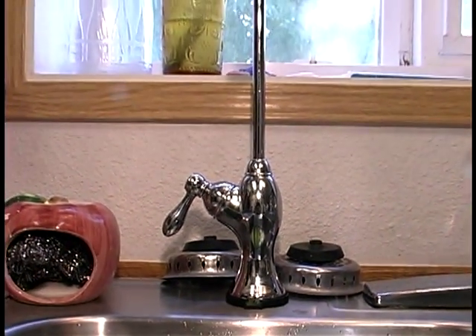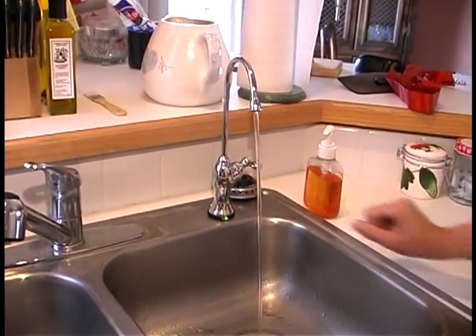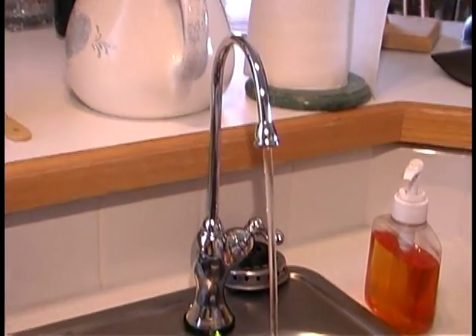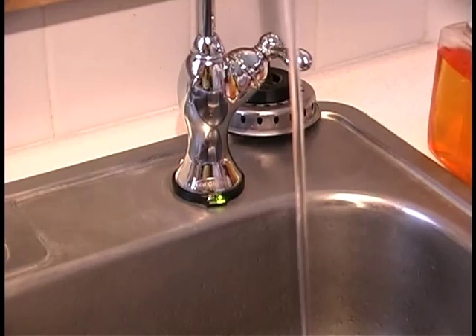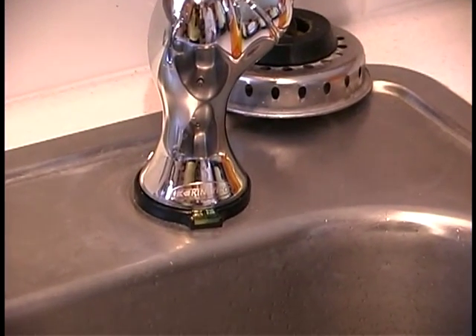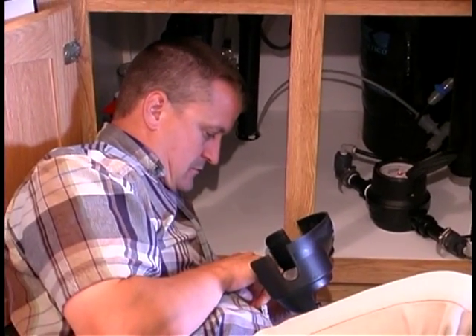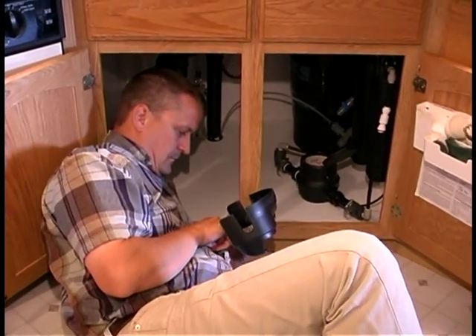The units have been in place for only a few months, but so far the homeowners are very satisfied with them. It's good that people know what's in their drinking water and know what to do to get rid of it. The units have a conductivity meter that, at a preset level, turns on a light to indicate to the homeowner that change-out of the RO membrane is needed. The units are owned and maintained by the homeowners' association. While large water systems would likely find it difficult to get into everyone's home on a regular basis for maintenance and filter replacement, access to the treatment units hasn't been a problem at this small system.